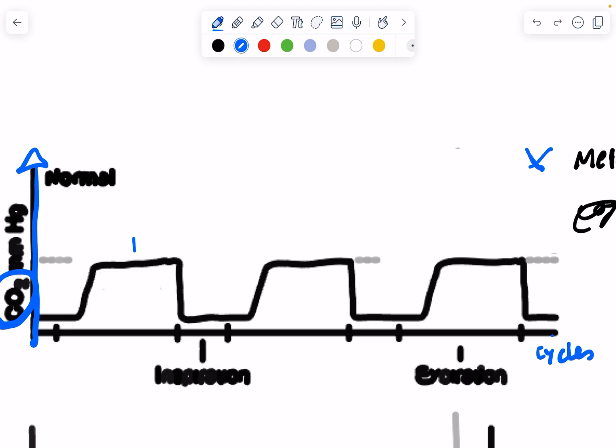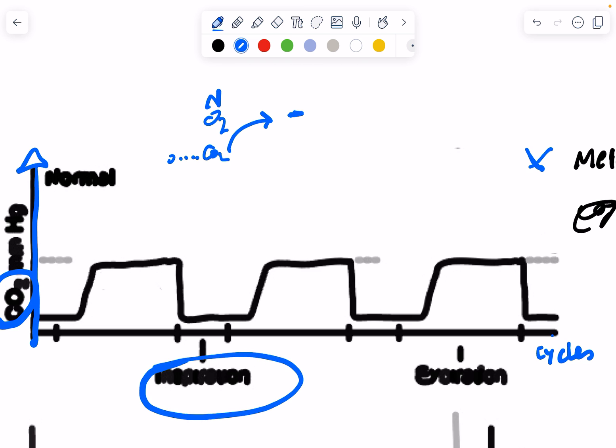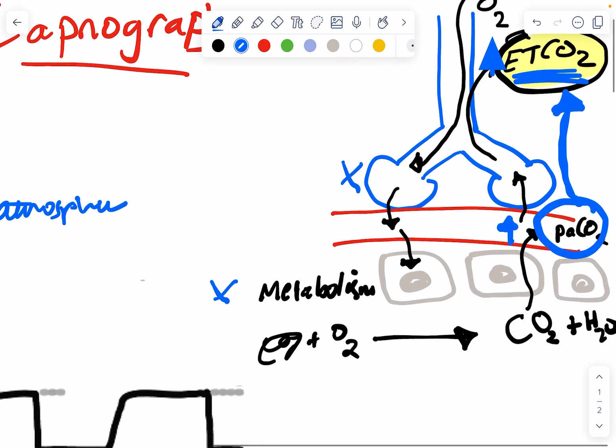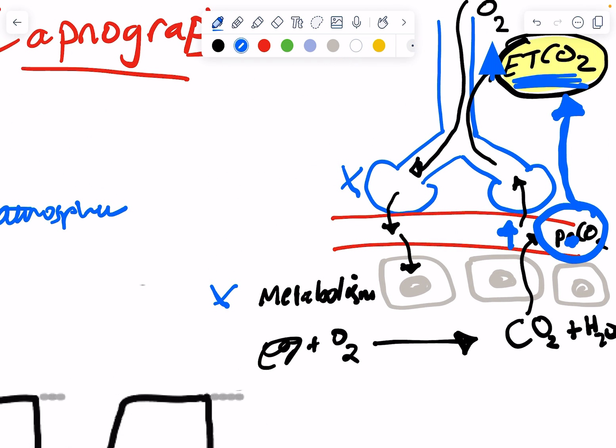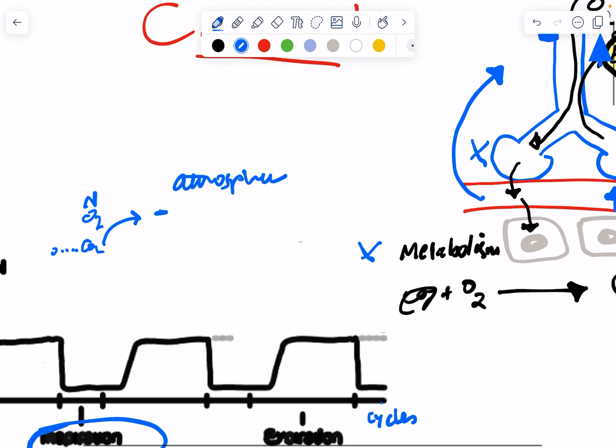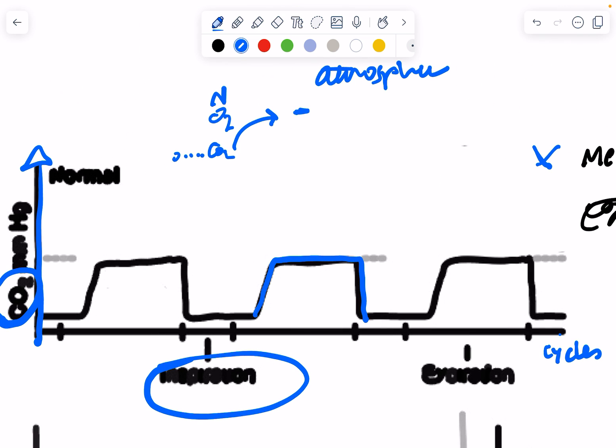And then we have one positive wave and one negative wave. A positive wave means CO2 is coming out and is measured by the device. And a negative wave means that we have less CO2 detected by the device. When the patient takes in a deep breath called inspiration, they're essentially not contributing any form of carbon dioxide to the detector because the air that you breathe in is mostly nitrogen, 78%, and oxygen with only very little CO2. So it's not going to contribute anything during inspiration. However, when you bring out carbon dioxide from your body, that's exhalation, it will be detected here by the detector. And that's why it shows us a positive wave with expiration.